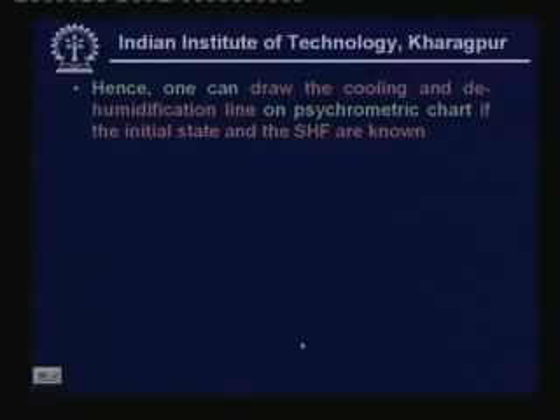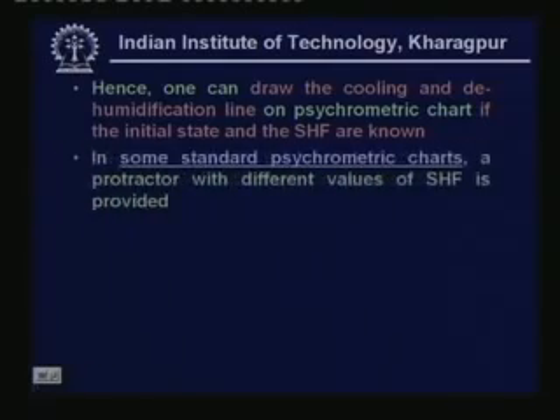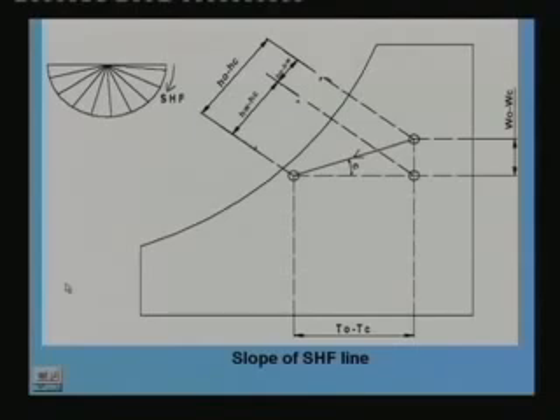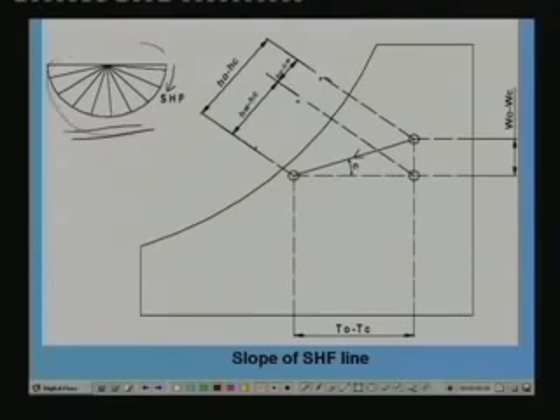Hence one can draw the cooling and dehumidification line on a psychrometric chart if the initial state and the sensible heat factor are known, because from the sensible heat factor you can find the slope of the line, and you also know the initial state. This line must pass through the initial state and you know its slope, so you can draw the process path. In some standard psychrometric charts, a protractor with different values of sensible heat factor is provided. This we will again discuss when we do the load calculations. So different values of these lines correspond to different values of sensible heat factor.